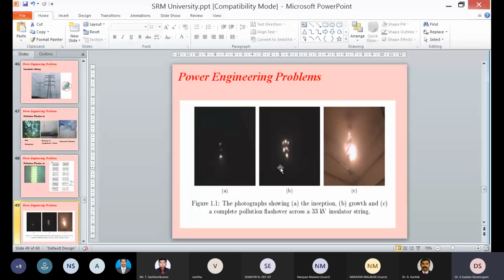So we cannot clear all the birds every time. We cannot say birds shouldn't sit there on the line and tower. Similarly, if there is an industry, we cannot tell the industry to move somewhere else. It is our duty to give supply to the industry. So what the Government of India decided is, wherever 220 kV and more than 220 kV lines are passing through the entire India, we have to create a database to know what is the level of severity available in the field condition. There are 4 levels: low severity, medium severity, high severity, and very high severity.